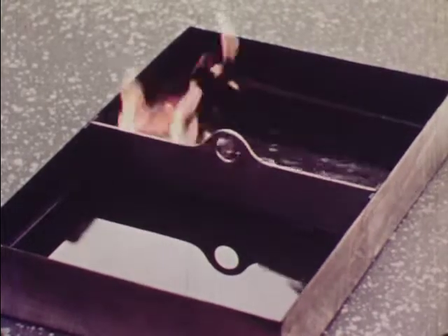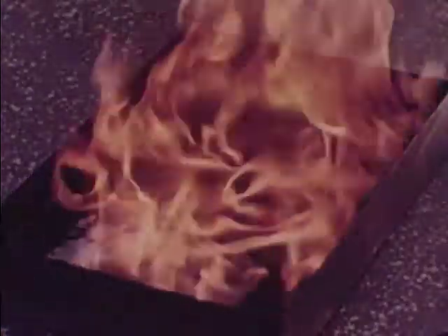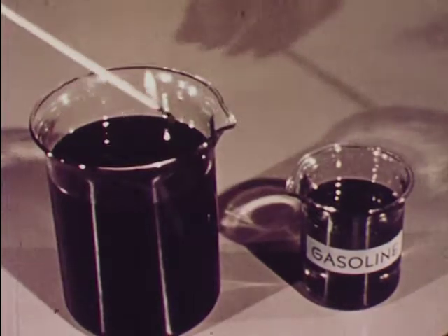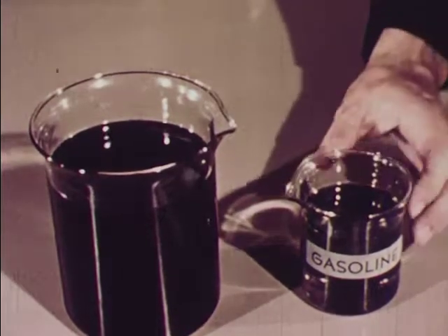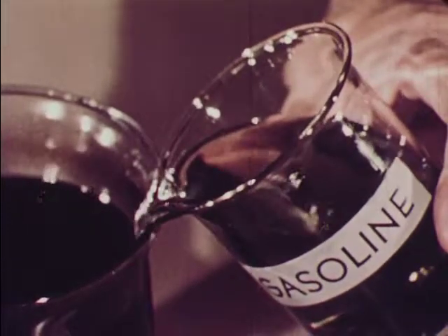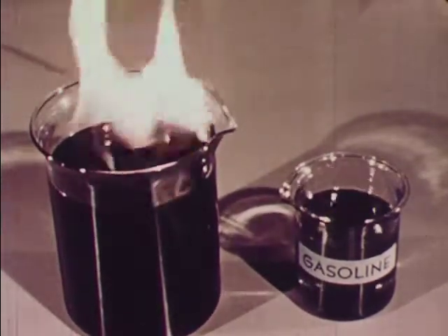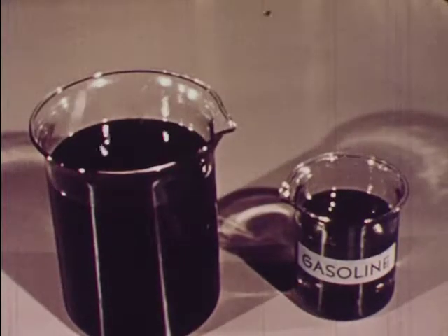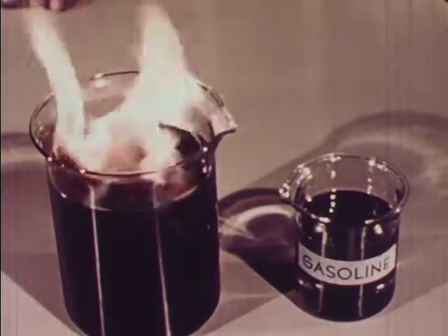Since the heat of its flame is greater than the ignition temperature of a fuel, a fire will spread rapidly once it has gained headway. However, a flame applied directly to this heavy fuel oil goes out because the temperature of the fuel oil is still below its flash point. By pouring a small amount of gasoline on the surface of the oil and igniting it, the heat of the flame is sufficient to raise the temperature of the heavy oil to a point where vapors are produced. These vapors then are readily ignited by the flaming gasoline.